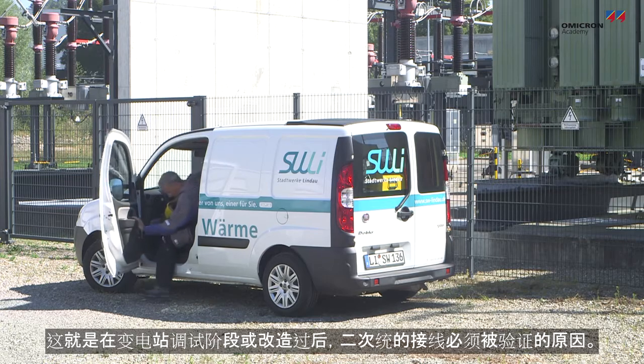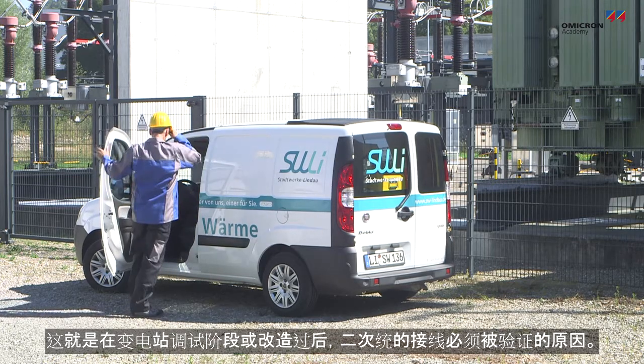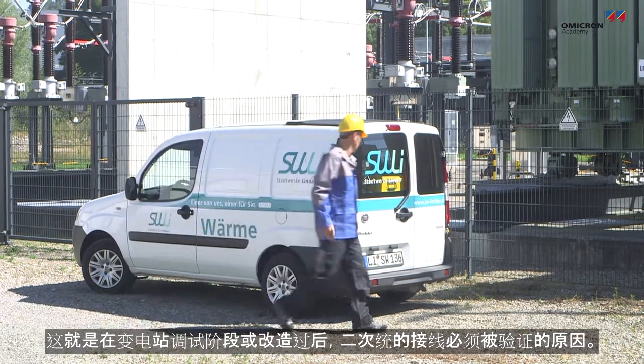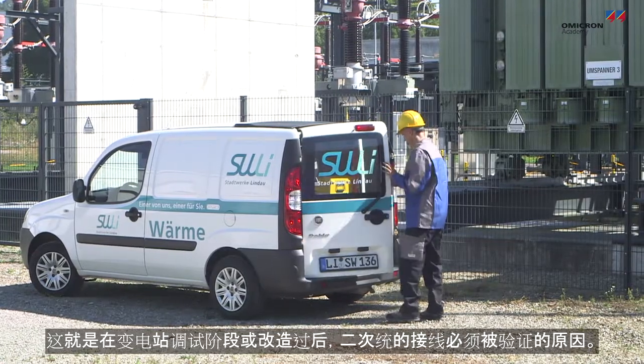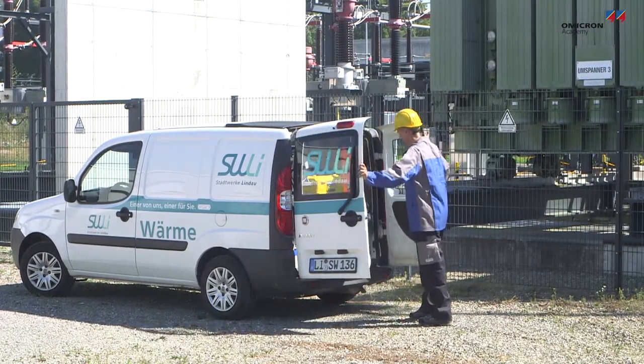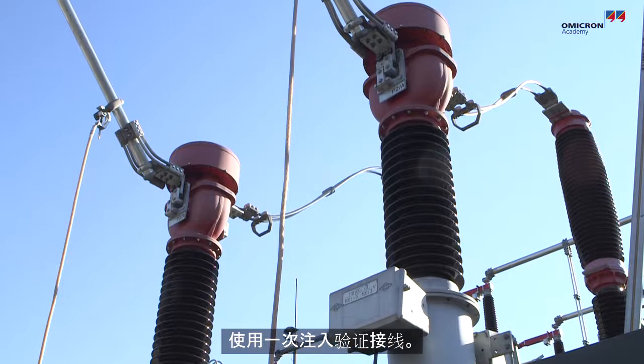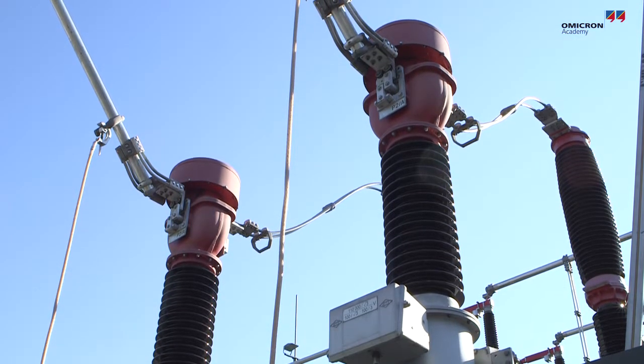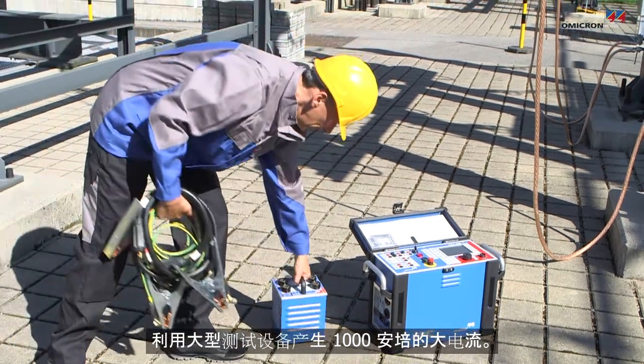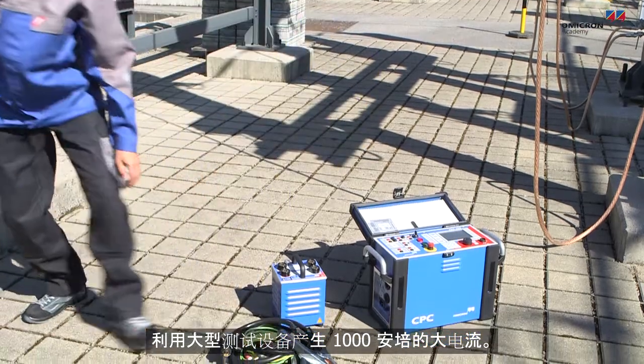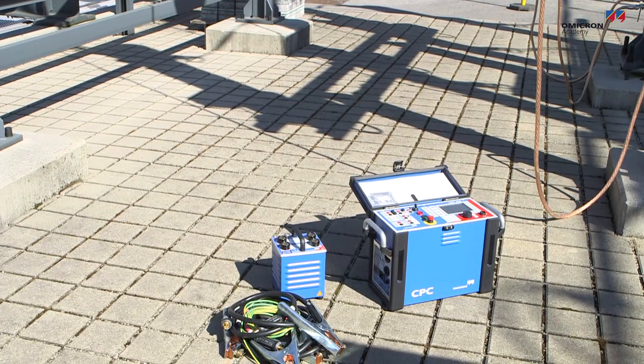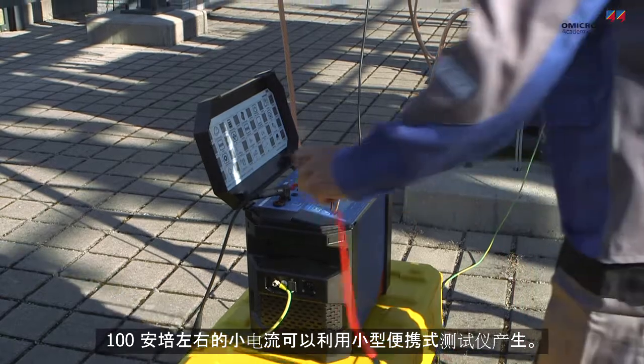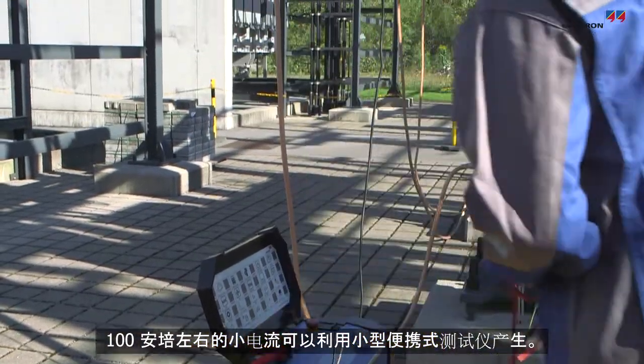This is why the secondary system's correct wiring has to be verified either during substation commissioning or after a refurbishment. Primary injection is used to validate the wiring. High currents of up to about 1,000 amps can be generated by larger testing equipment. Smaller currents of about 100 amps can be generated by smaller and more portable test sets.